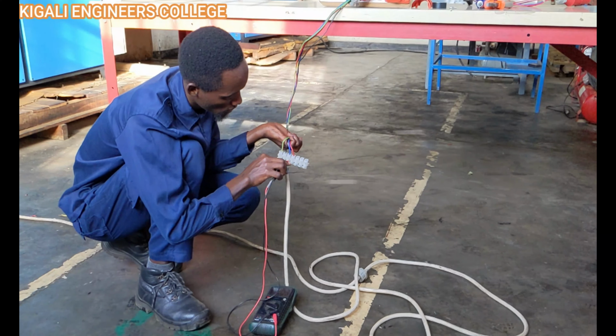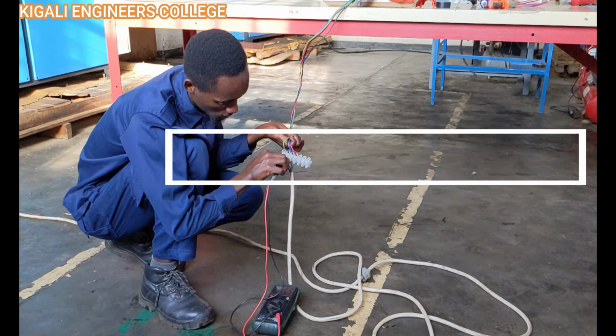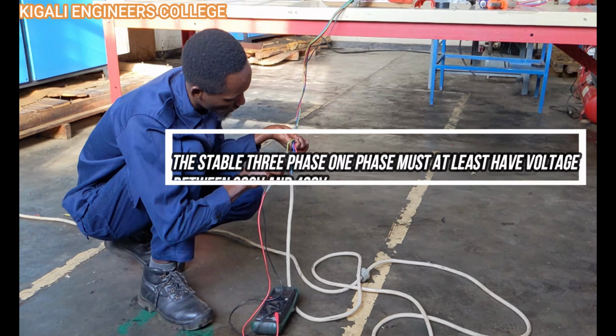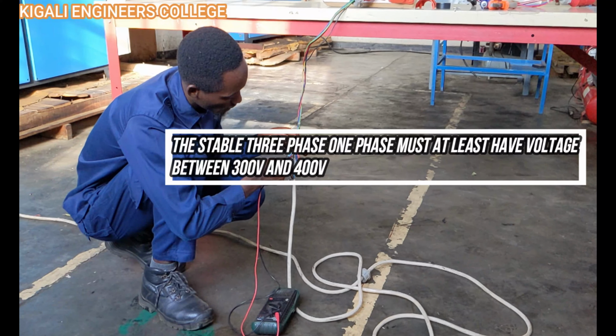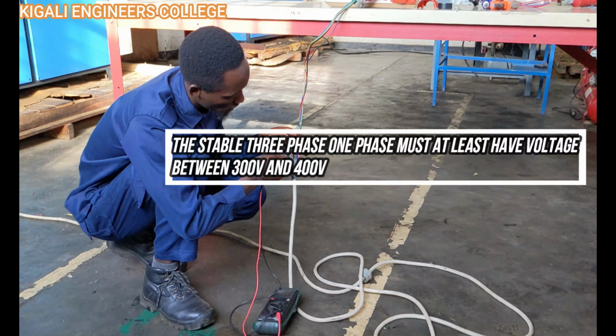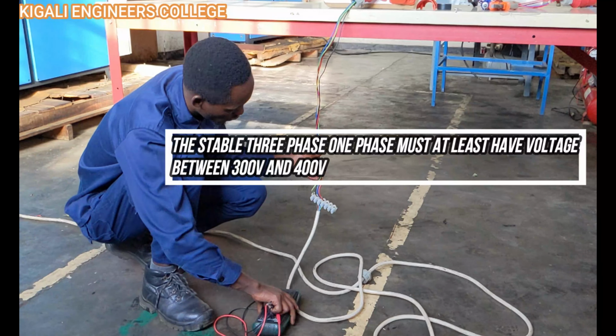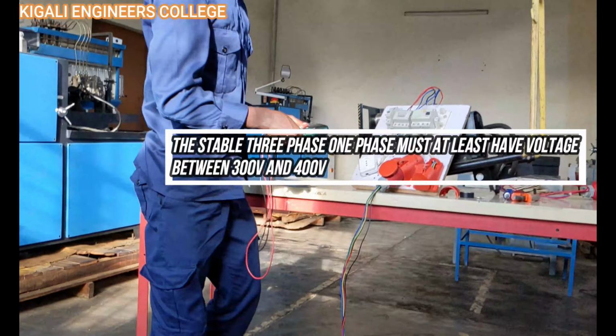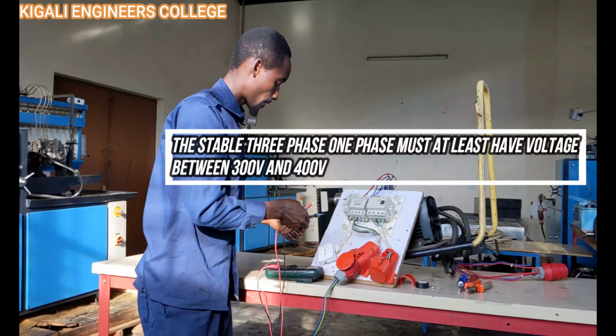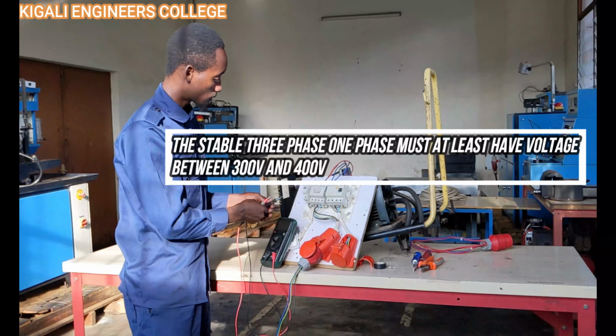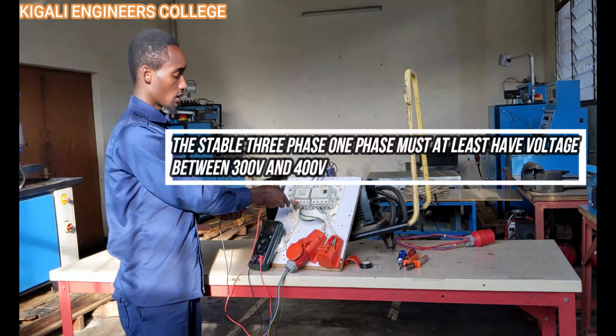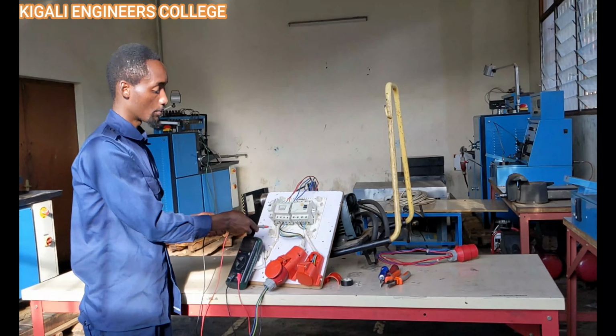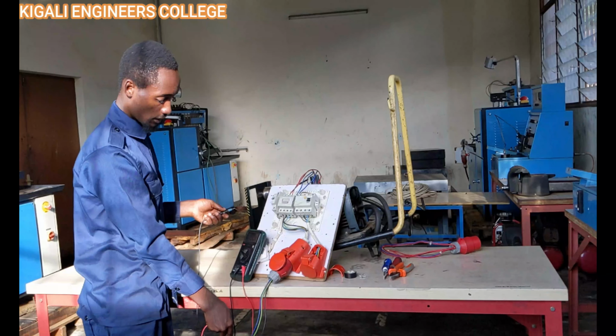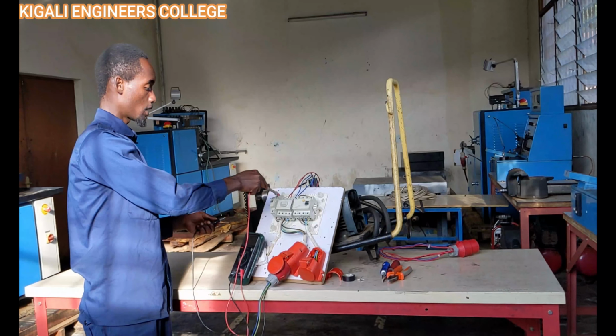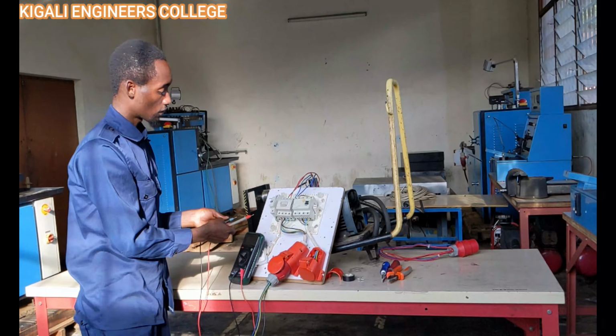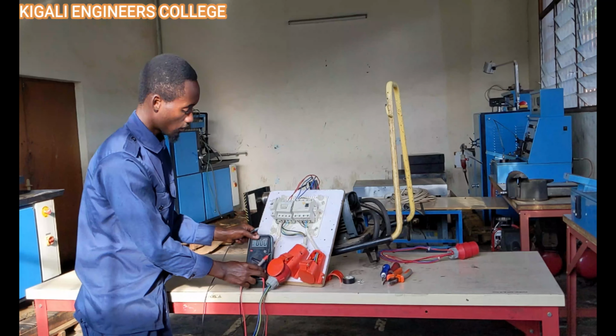100, and also 67. So for phase 2, it means they have unstable voltage. Also at this input of the circuit breaker, the current passes through this wire to this 3-phase circuit breaker, and we measure it too.